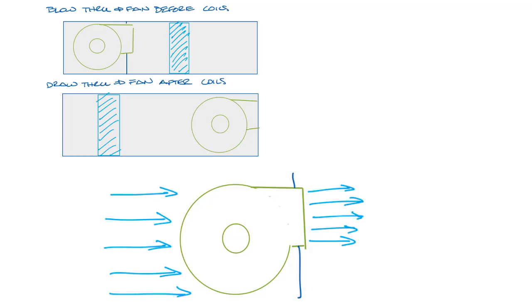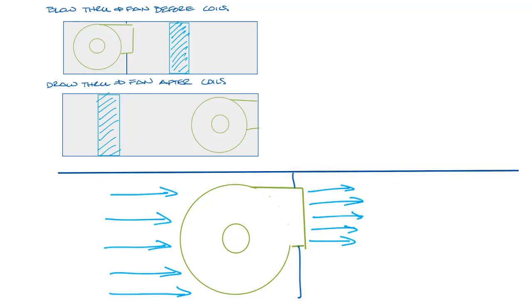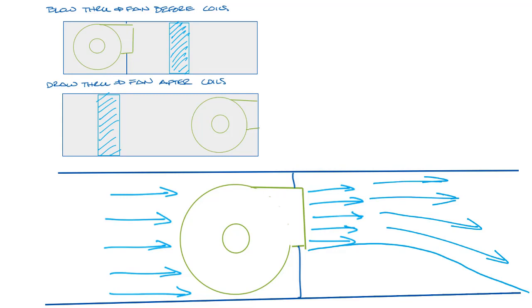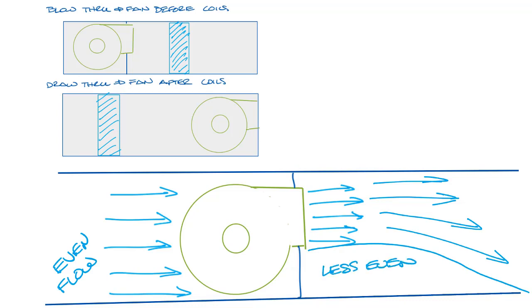So if I draw a casing in so you can look at it as if it were inside an air handler, you can see that the air coming out the discharge is going to come out at top and kind of expand as it moves through the unit. So you can see that the flow on the inlet side is much more even when compared to the flow on the discharge side of the fan, at least right at where the fan is discharging.